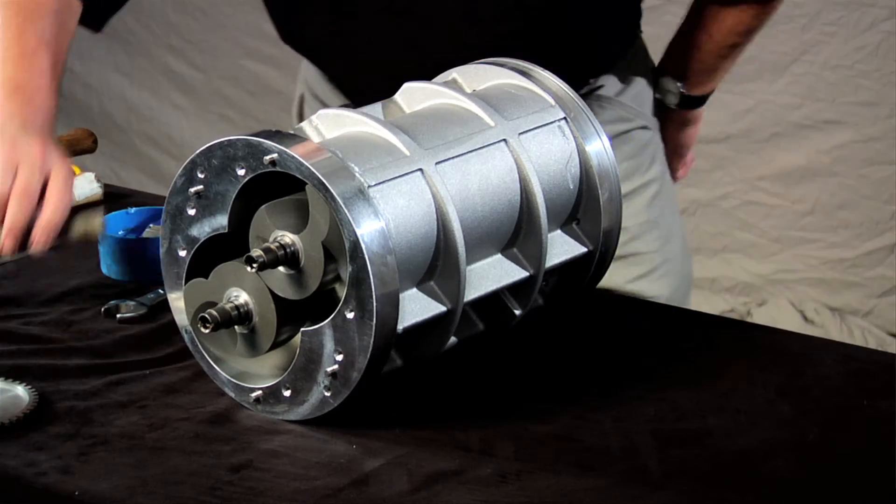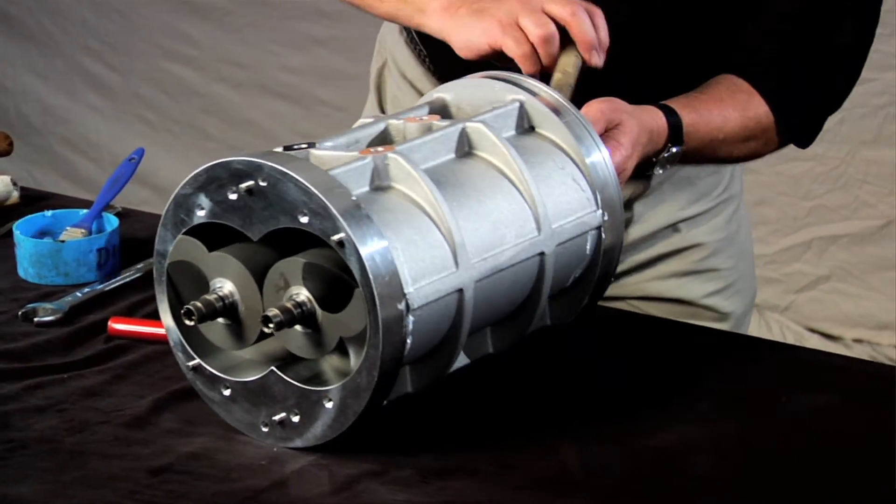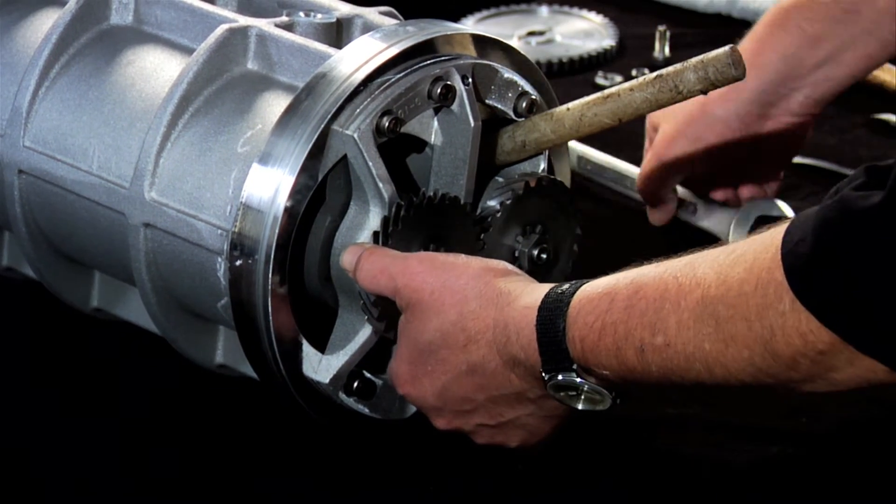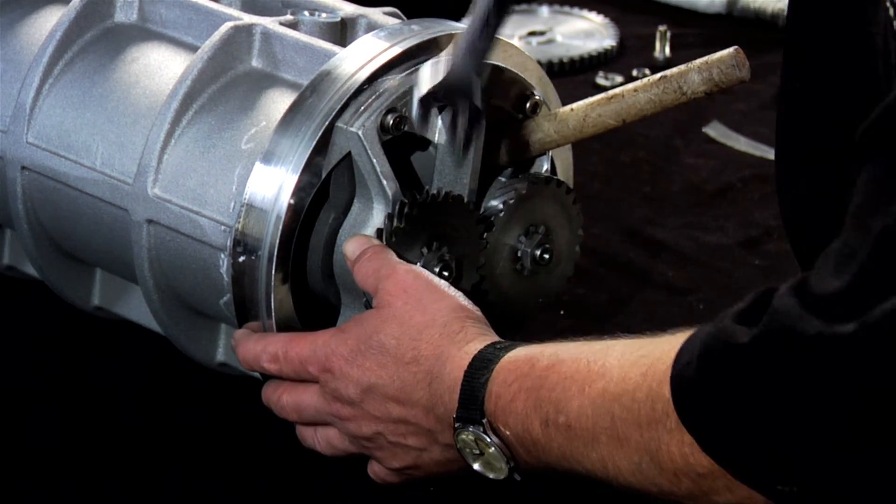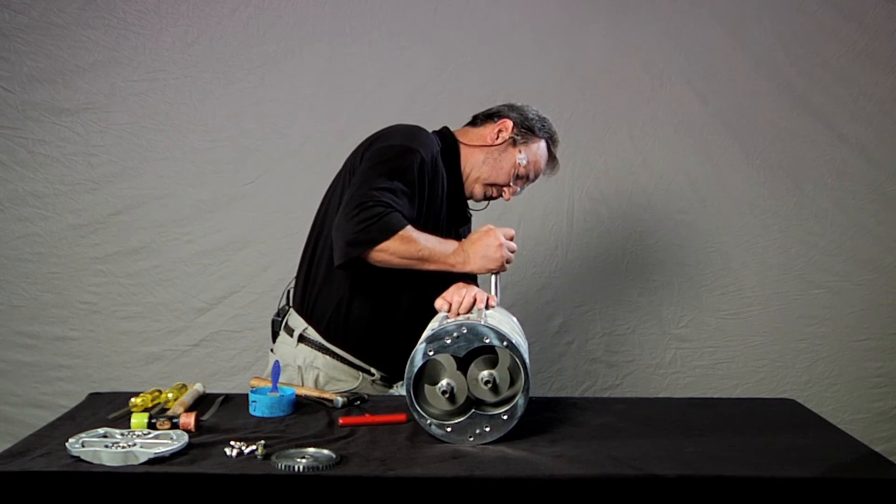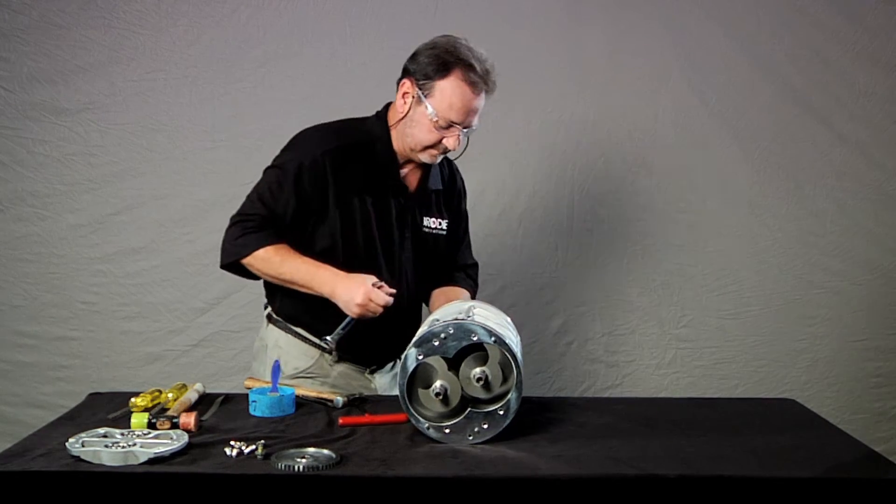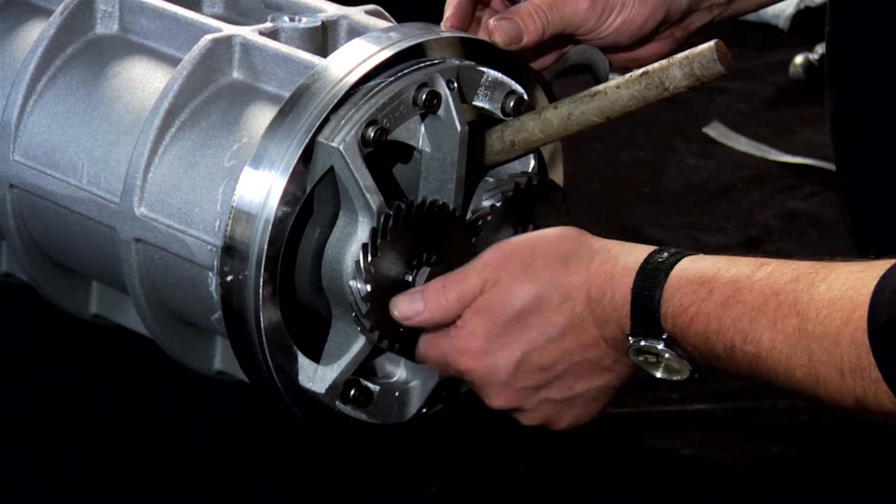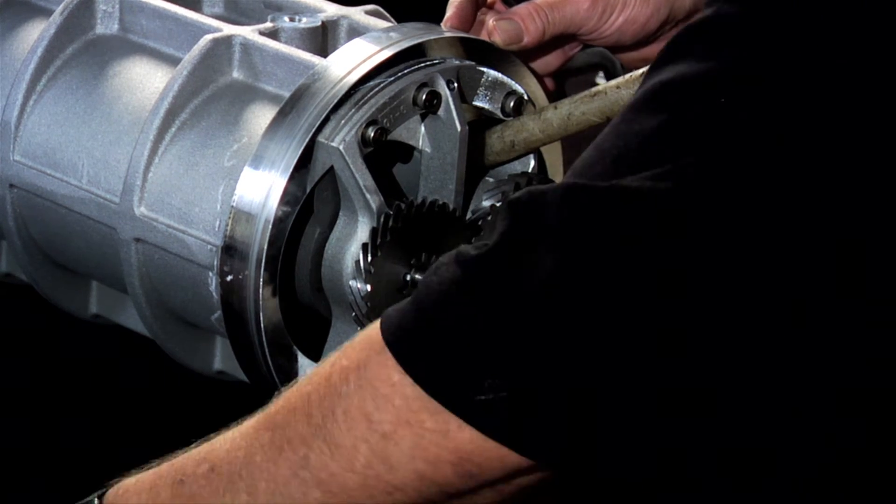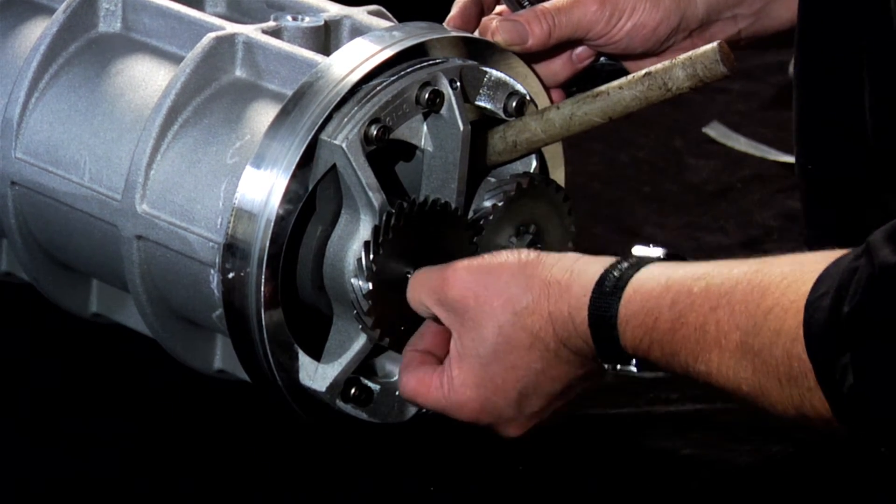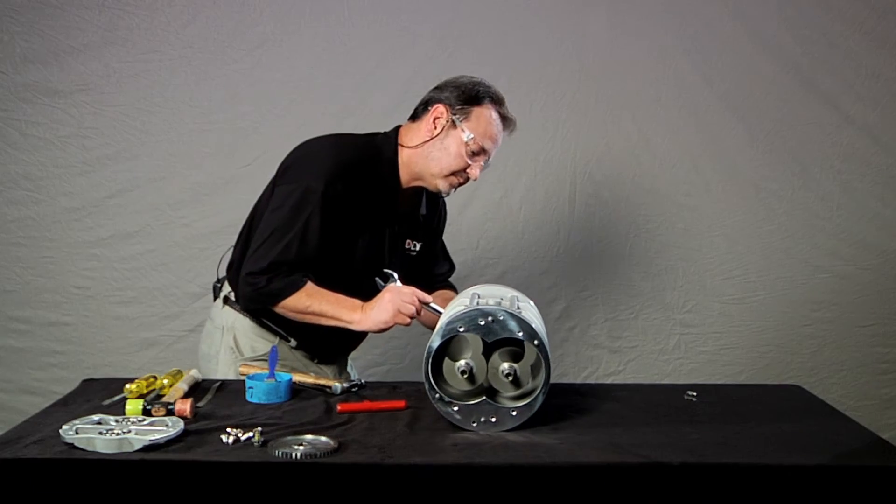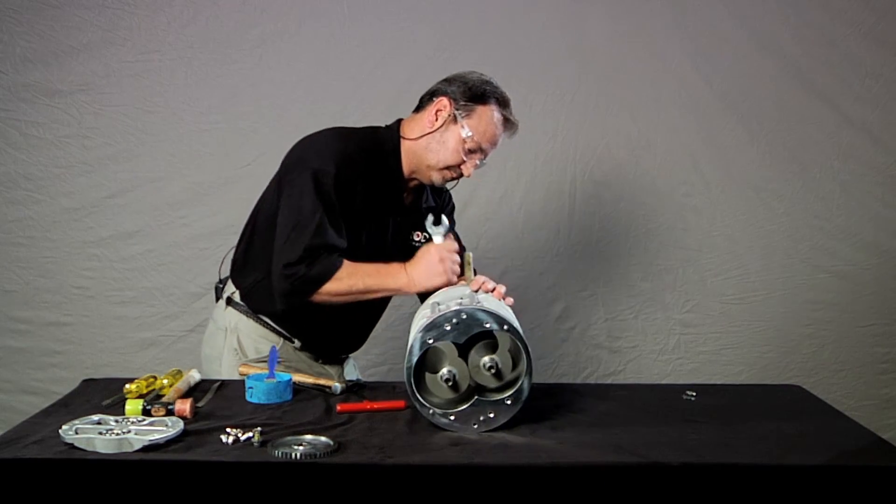On the opposite end of the measuring unit, you'll find the timing gears. Again, insert the blocking stick to stop the rotors from turning and loosen the lock nuts with the wrench. Remove the lock nuts and locking rings. Remove the locking stick.